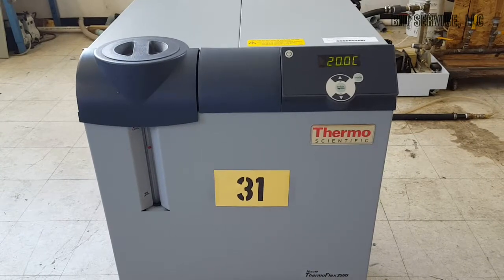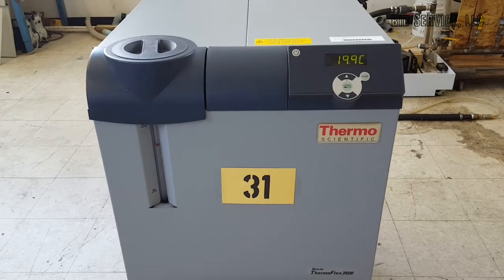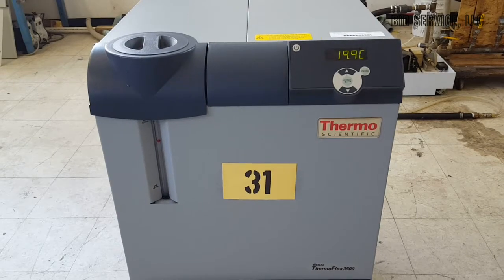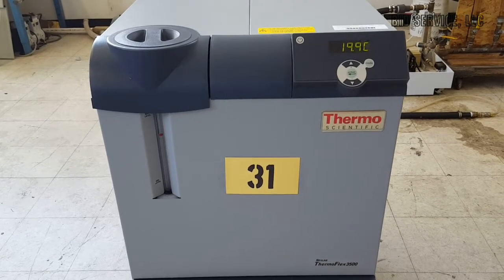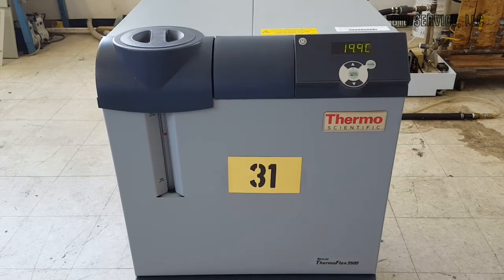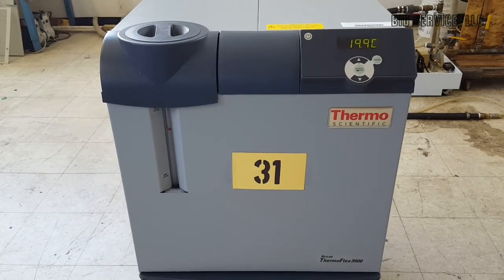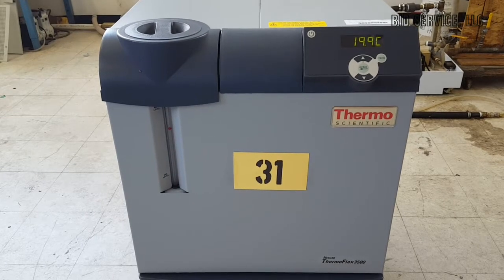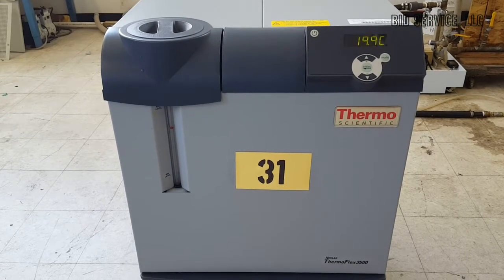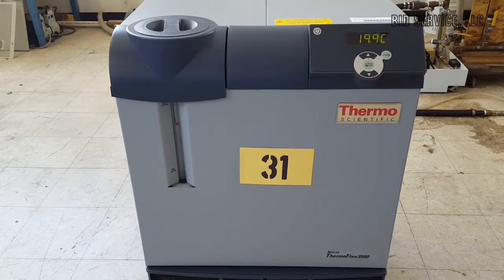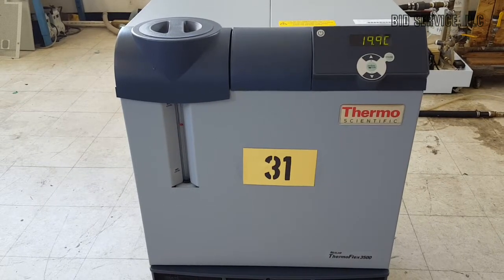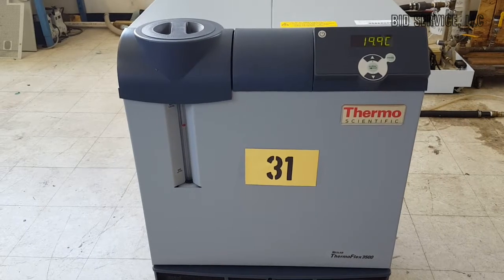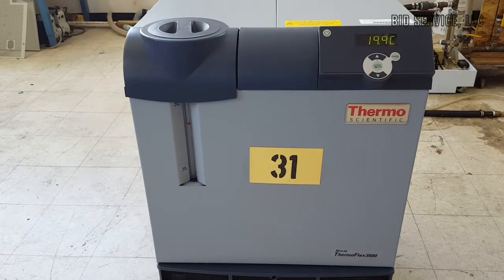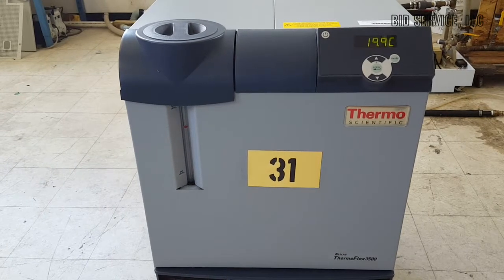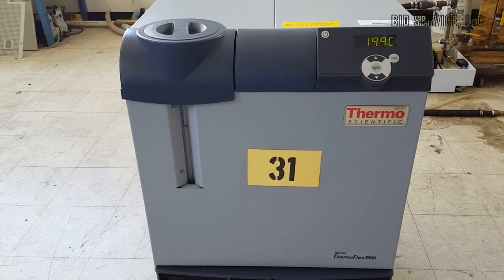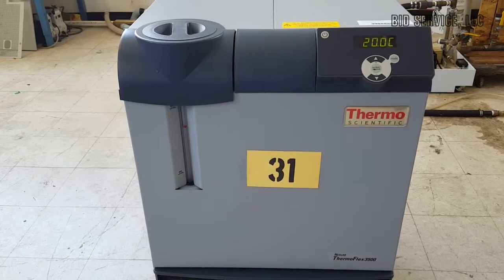A demonstration of the Neslab Thermoflex 3500 air-cooled refrigerated recirculating chiller. It has a temperature range of between +5 to +40 degrees C, a cooling capacity at 20 degrees C of 3,500 watts. The reservoir volume is 1.9 gallons with a pumping speed of 4 gallons per minute at 60 psi. It is powered by 200 to 230 volts AC, single phase, 11.9 amps.